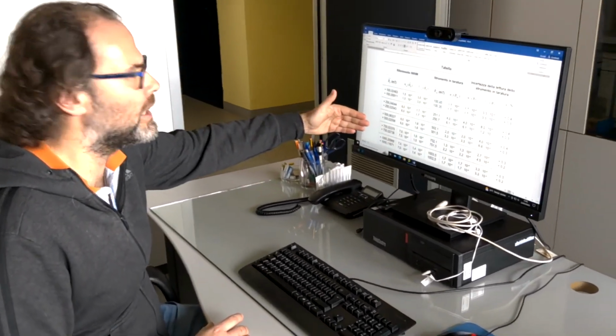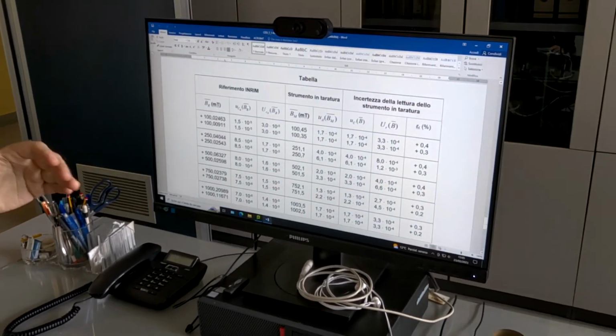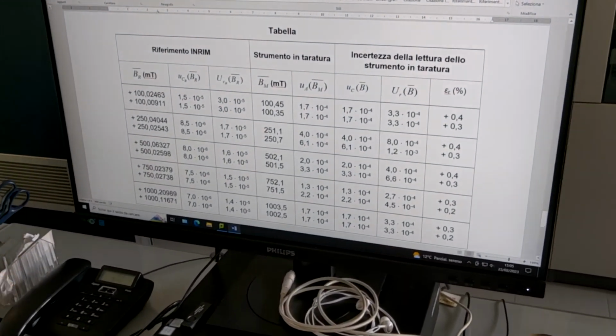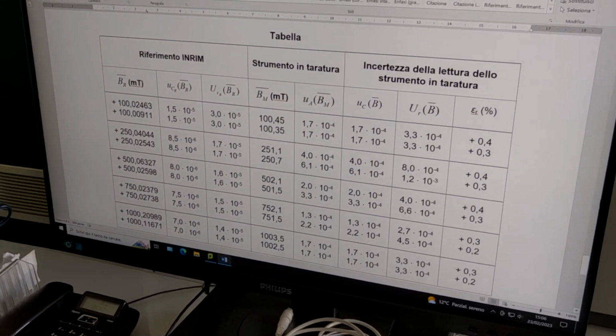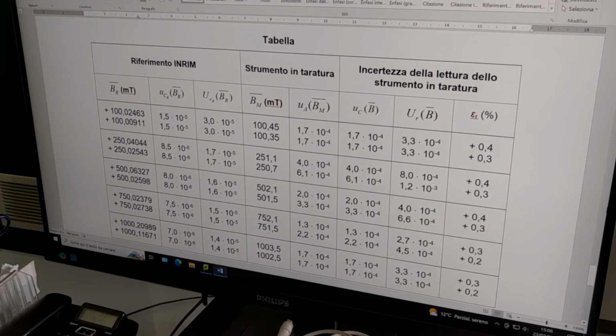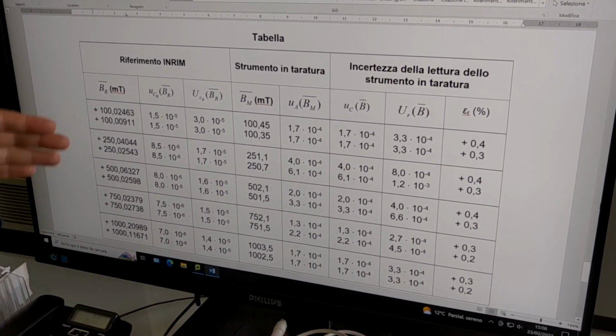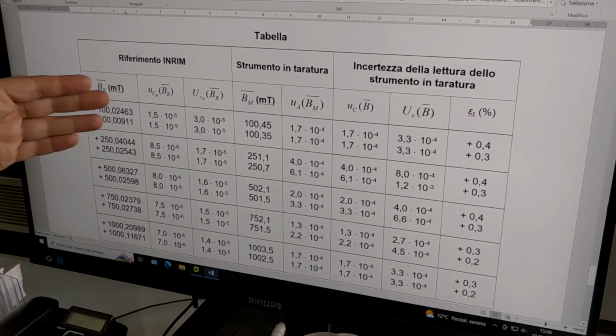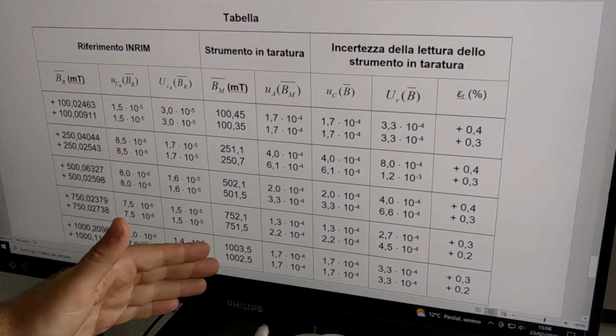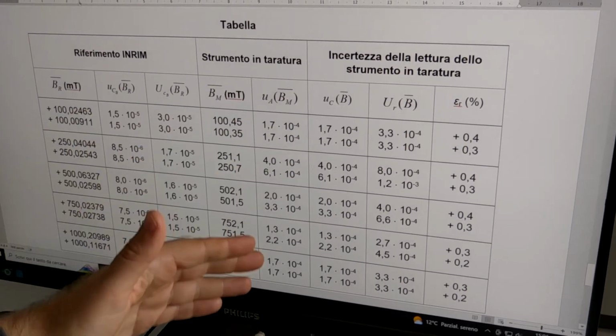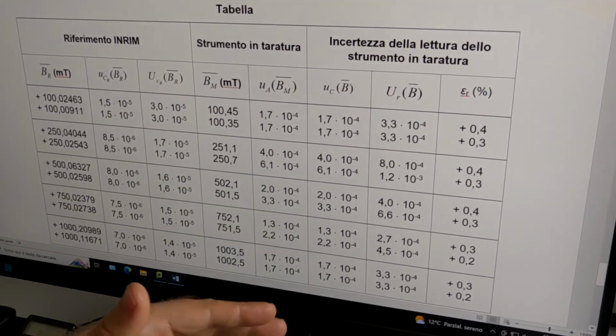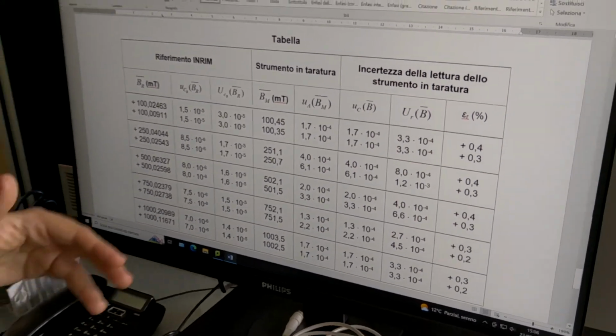In order to do the calibration, we repeat the measurement procedure a certain number of times. For example, here we have selected 5 different applied field values. We have also repeated the measurement 2 times for each applied field value, by removing both probes and putting them back in the magnet in order to take into account possible fluctuations in the positioning of the probes. For each field value, then, we have the reading of the nuclear magnetic resonance instrument with the associated uncertainty. Then we have the reading of the unknown probe with the associated reading uncertainty, and then we combine the uncertainties so that we come up with the final field value with the associated extended uncertainty and the discrepancy between the reference value and the value measured by the unknown probe.